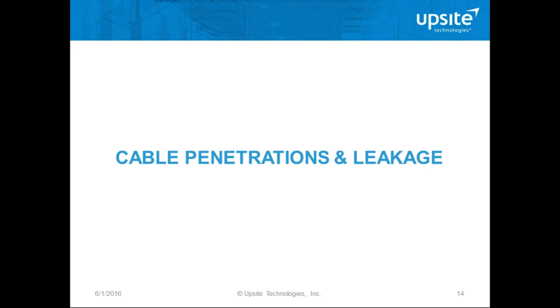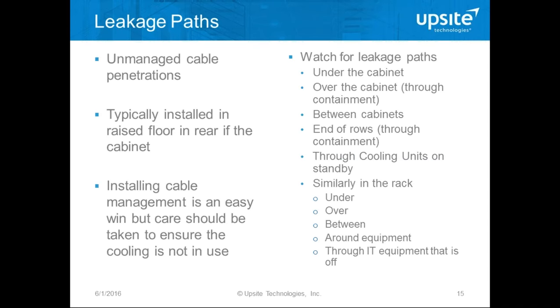One of the most common methods of management is managing leakage through cable penetrations. Cable penetrations are typically unmanaged in legacy data centers, and they're installed in the raised floor in the rear of a cabinet. If there is leakage, the cold air leaks straight into the hot side of the rack, not doing any useful work — it's bypassing. We can install cable management as an easy win, but we must take care. Leakage management is appropriate for both the room and the rack — we're doing the same things in both, preventing cold air from getting into the hot side and vice versa.